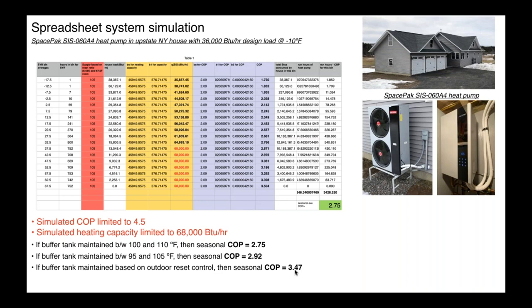The geo has a higher number. End of story. It's not the end of story. What really counts when you're looking at these systems is not, bottom line, that COP. If you look at your utility bill, you will not see a line on there that charges you for COP. You will see a line that has kilowatt hours. So it really comes down to how many kilowatt hours a given approach saves you. That's what you're paying for.